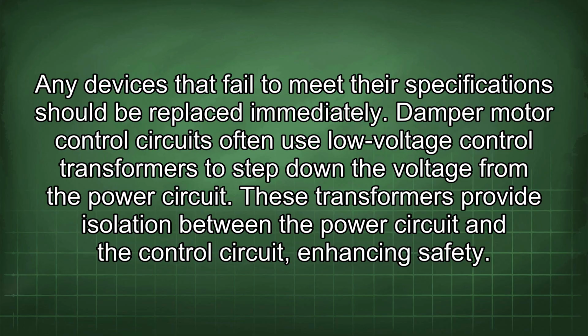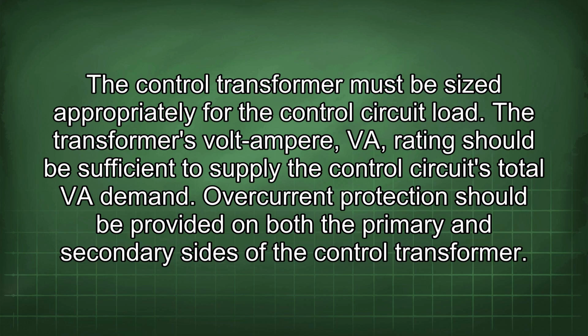Damper motor control circuits often use low voltage control transformers to step down the voltage from the power circuit. These transformers provide isolation between the power circuit and the control circuit, enhancing safety. The control transformer must be sized appropriately for the control circuit load. The transformer's volt-ampere (VA) rating should be sufficient to supply the control circuit's total VA demand.